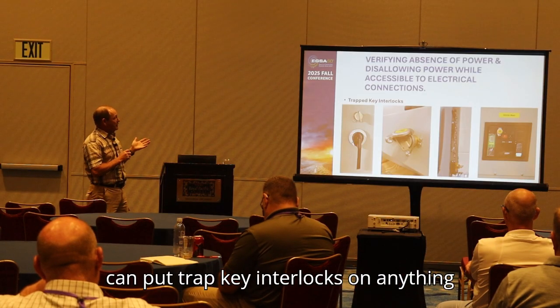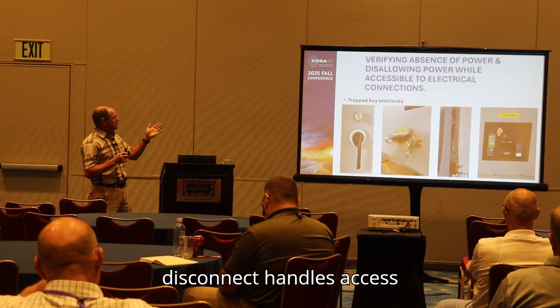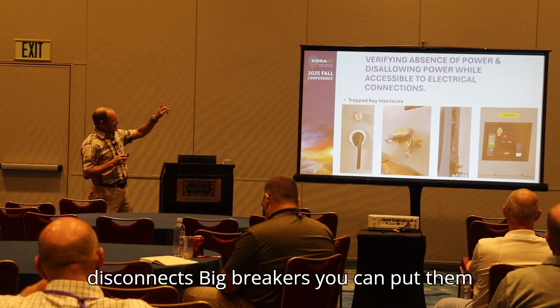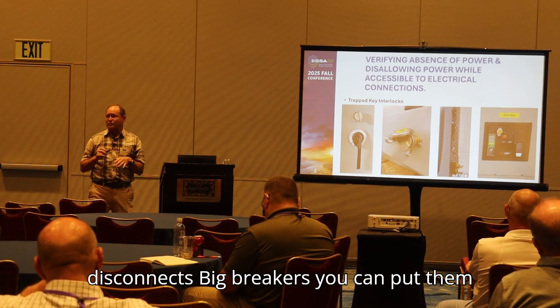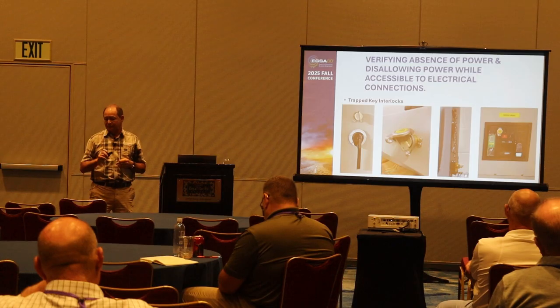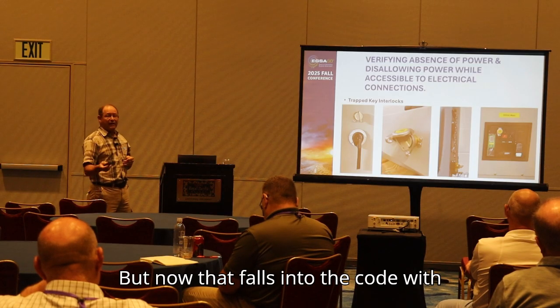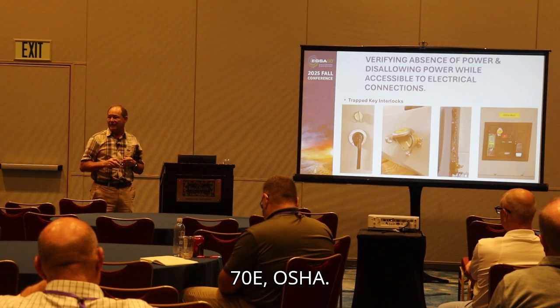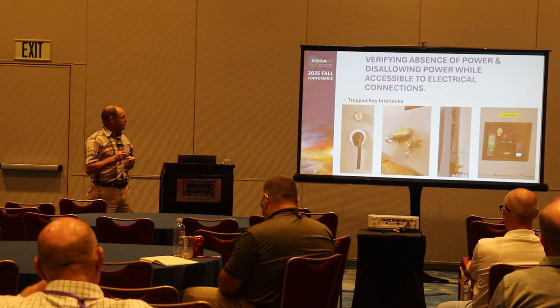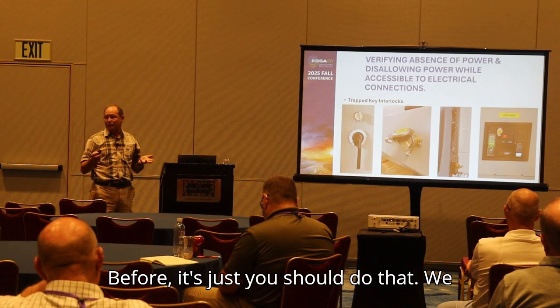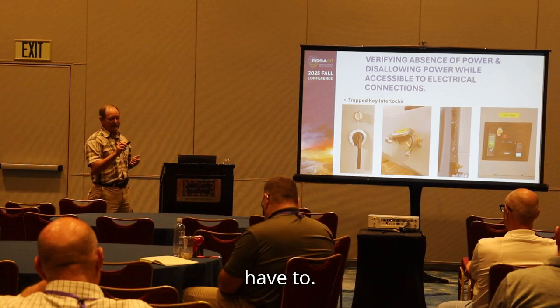Not that we didn't make it better, but you can put trap key interlocks on anything. Disconnect handles, access, disconnects, big breakers, you can put them on anything now. But now that falls into the code with 70E, OSHA. Before it's just, you should do that. We knew it was stupid, so we did it. Now you have to.